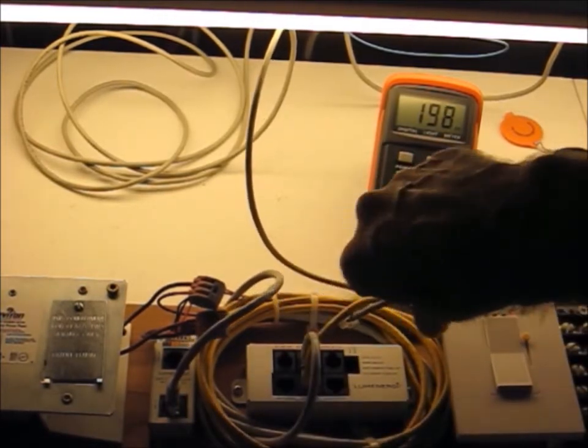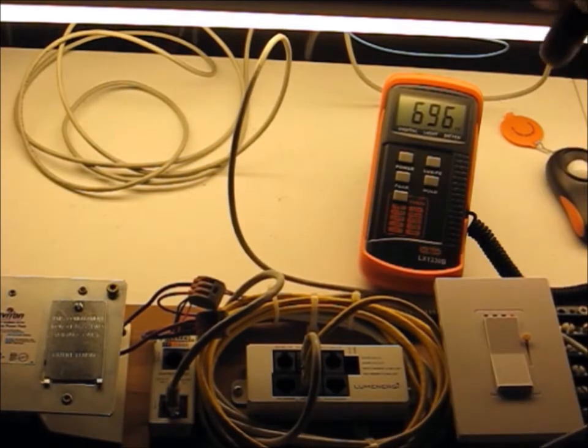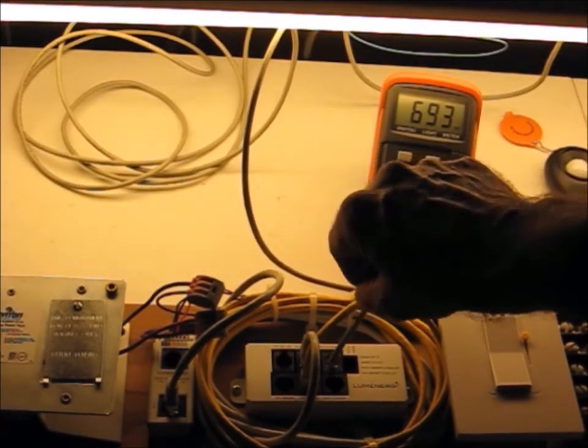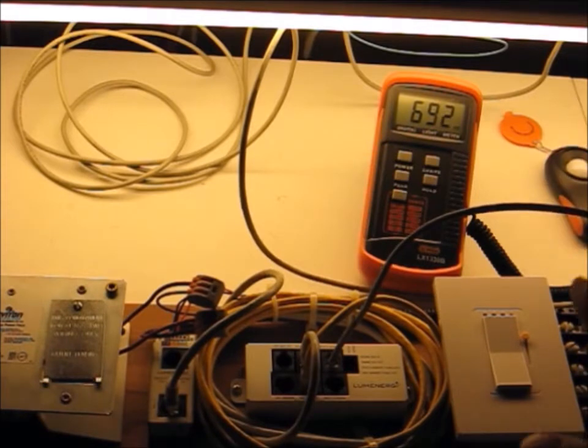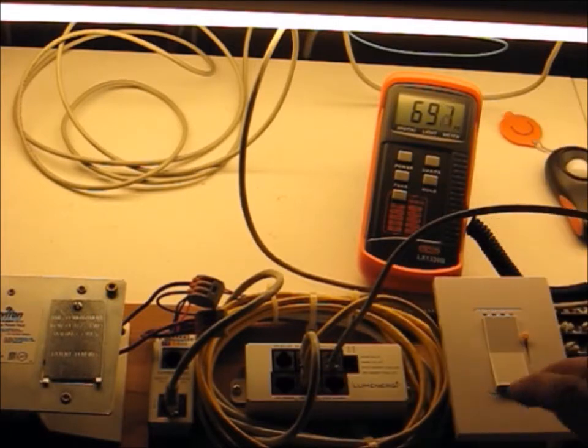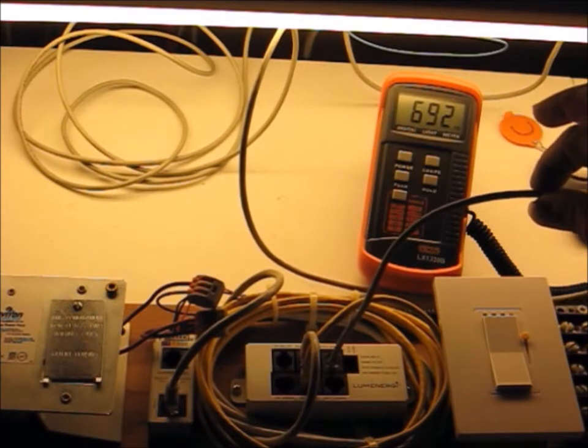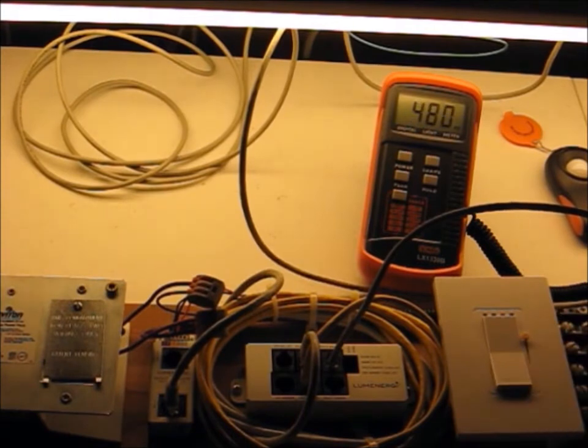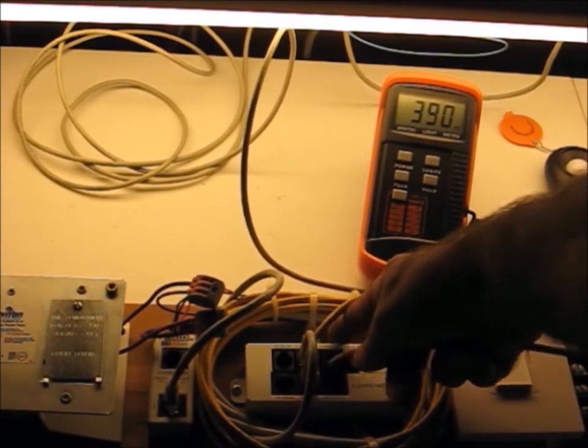And how does this ballast respond to losing its DALI bus? If I unplug it, it goes to full power. That's programmed into the ballast and in most of these things you can change that. Plug the DALI ballast back in, it doesn't do anything, and the reason for this is a command has not been issued. In a standard short address DALI system, there's only a signal on this line telling the ballast what to do when a command is issued. So reconnecting the DALI bus but not reissuing a command doesn't do anything. The ballast stays at its pre-programmed 'hey I've lost my DALI bus' level.